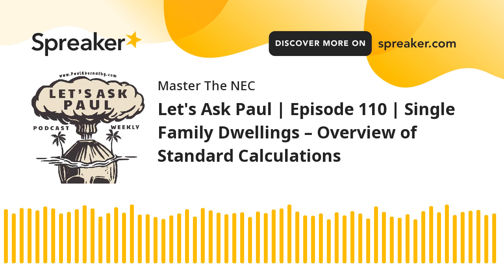Find the largest motor. Now, we're not doing that for all the motors. Just the first motor, just like what it says in 430.24. We only need to do this for one. I can tell you this blows people's minds because when we do multifamily dwellings and there's like a 10-story building with 10 units and we go looking for the largest motor, folks want to do this for every floor. They're like, well, I got 10 units, Paul, I got to take every one of them at 125%. No, just the largest one. That's it. Just one. Not all 10, just one.